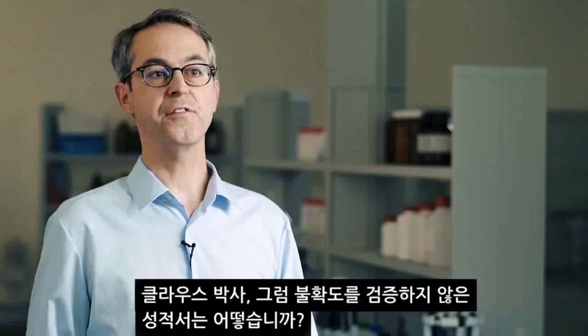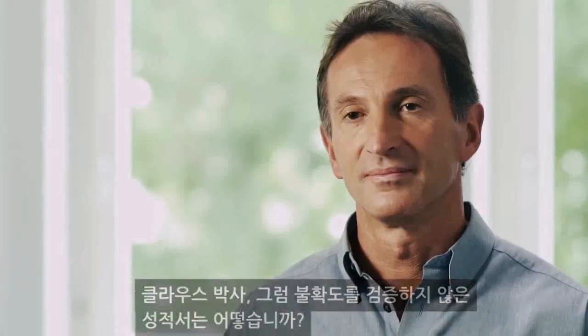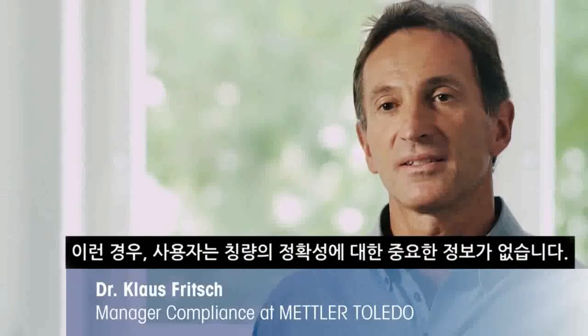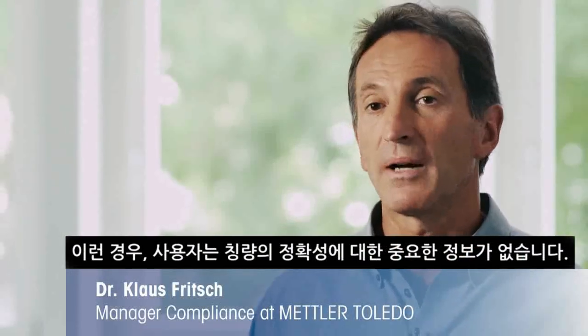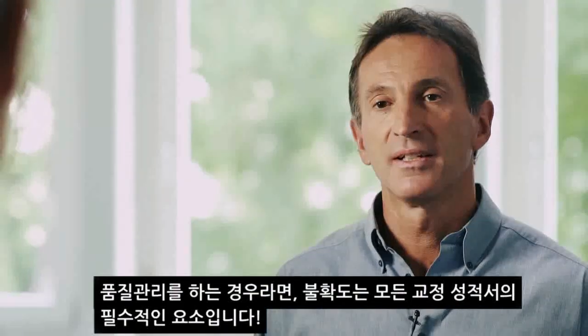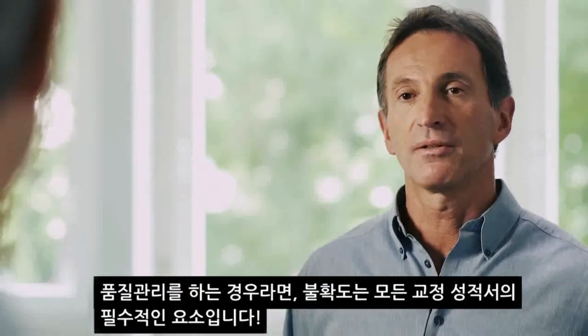Klaus, what about certificates that do not contain uncertainty? In those cases, users lack critical information about the accuracy of the weighing process. If you want to control quality, uncertainty is a critical element of every calibration certificate.